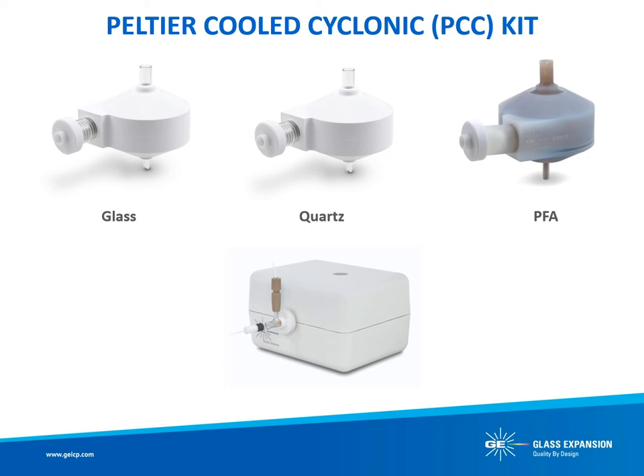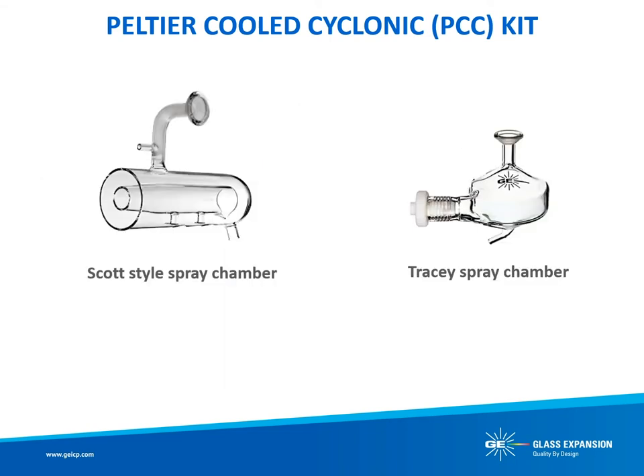The advantage of a cyclonic spray chamber over a Scott-style spray chamber is twofold. First, faster washout: the cyclonic design has dramatically lower surface area and volume from which to remove the previous sample. Second, more efficient removal of large droplets — unlike a Scott-style spray chamber, a cyclonic spray chamber uses centrifugal force to impact large droplets on the spray chamber wall. On the next couple of slides we'll see a comparison of these two spray chambers on the same instrument.